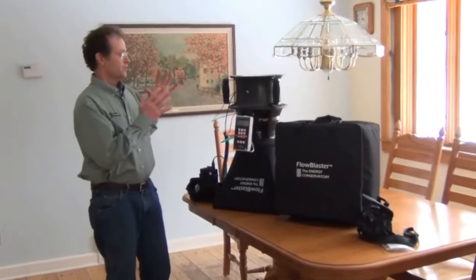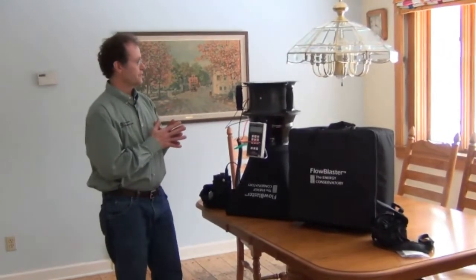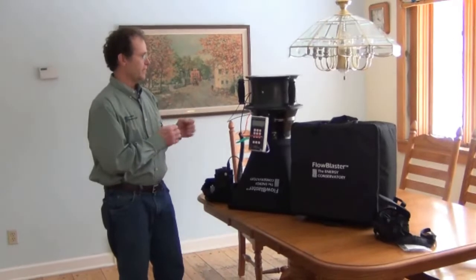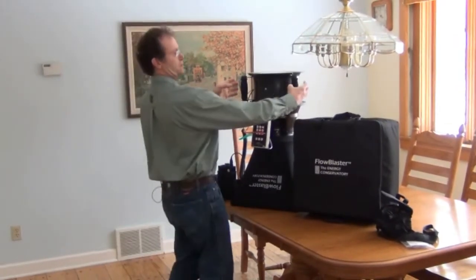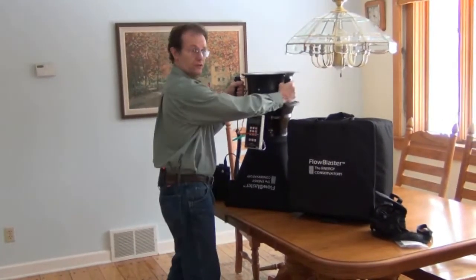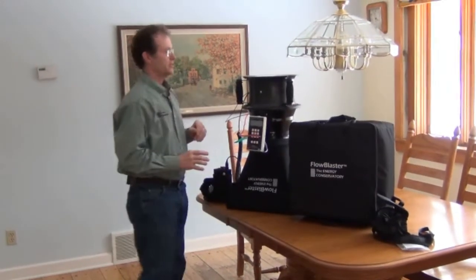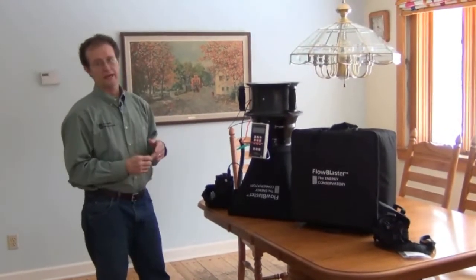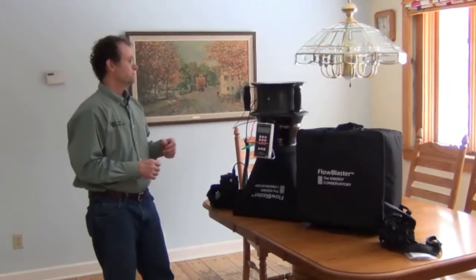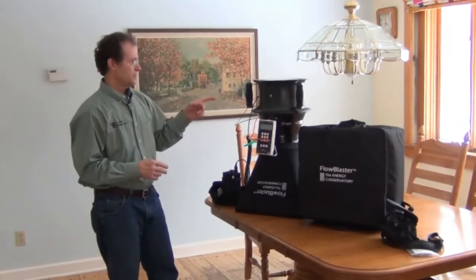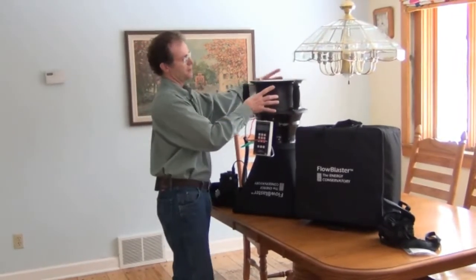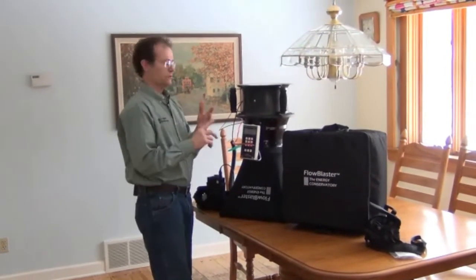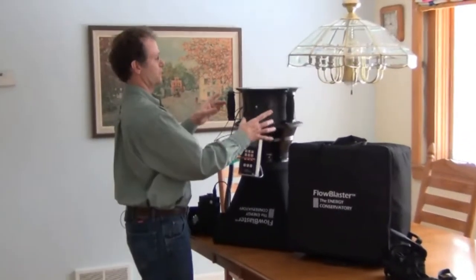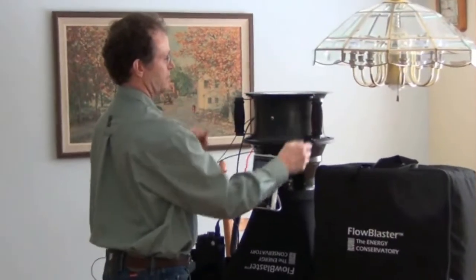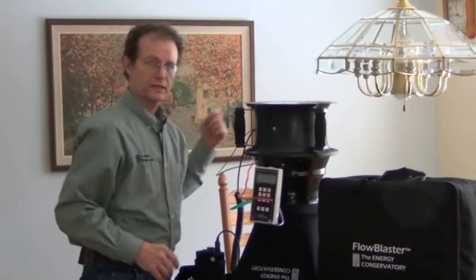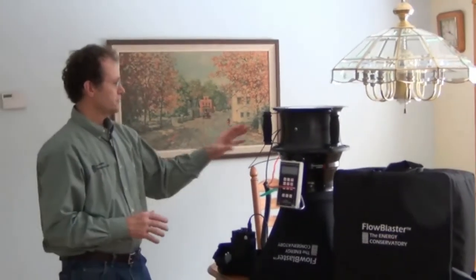So we're measuring supply registers today. So we've set up the Duct Blaster fan to measure supplies. The kit does come with handles, so you'll need to attach the handles on your existing Duct Blaster fan, and then the handles can remain on. So the way we set this up is I put a flow ring on here first. We need to use either ring 2 or 3, and I used ring 3. I put ring 3 on. Set the fan on top of it, and then put the connector, just like you connect a flow ring on there. So that's all set up.